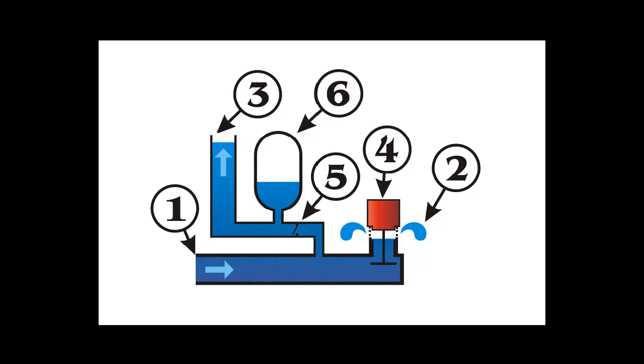Another solution is to have a mechanism such as a snifting valve that automatically inserts a small bubble of air when the suction pulse reaches the pump. Another solution is to insert an inner tube of a car or bicycle tire into the pressure vessel with some air in it and the valve closed. This tube is in effect the same as the diaphragm, but it is implemented with more widely available materials. The air in the tube cushions the shock of the water the same as the air in other configurations does.